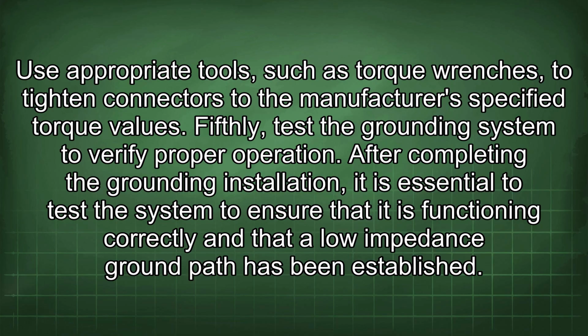Fifthly, test the grounding system to verify proper operation. After completing the grounding installation, it is essential to test the system to ensure that it is functioning correctly and that a low impedance ground path has been established.